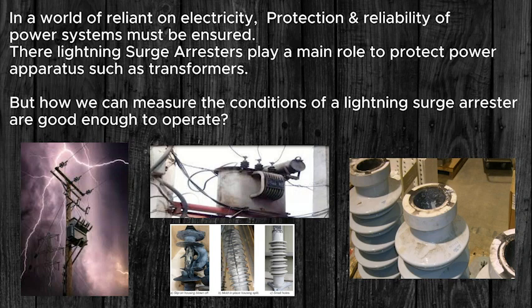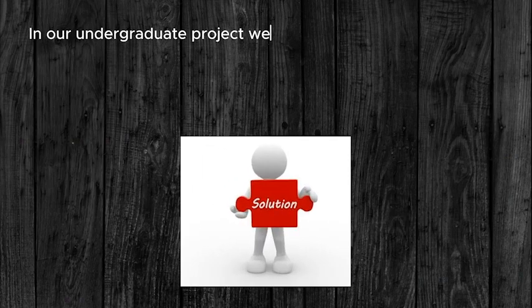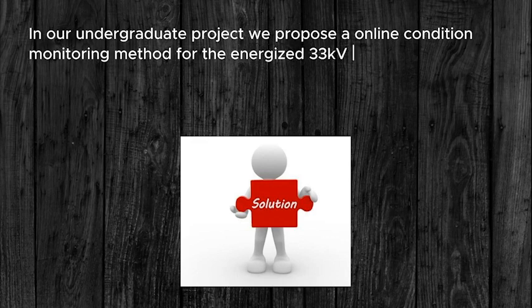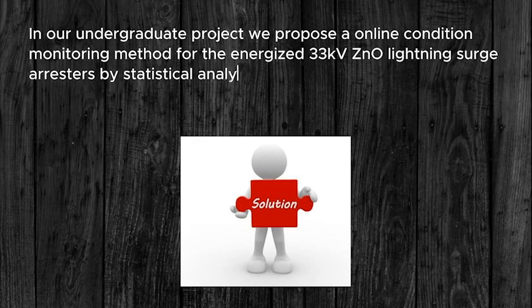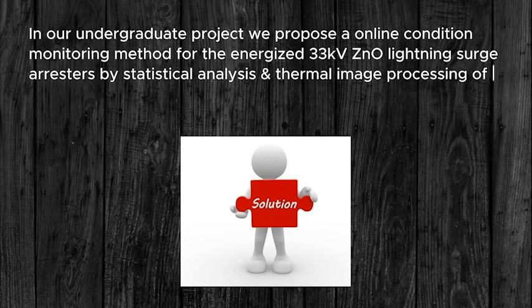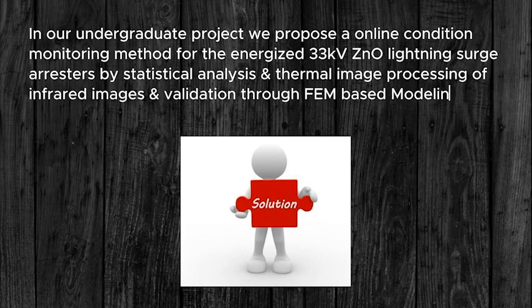In our undergraduate project, we propose an online condition monitoring method for the energized 33 kilovolt zinc oxide lightning surge arresters, using statistical analysis and thermal image processing of infrared images, and validated through FEM-based modeling. Under our methodology, we are going to verify the condition of a surge arrester in two different ways.